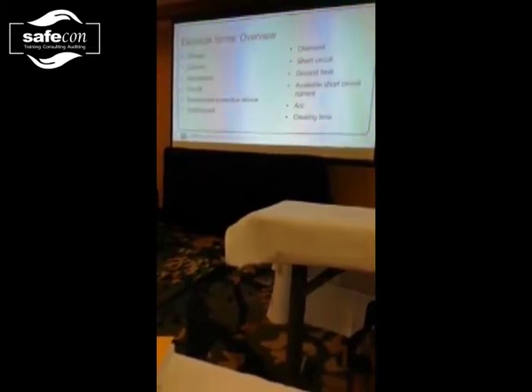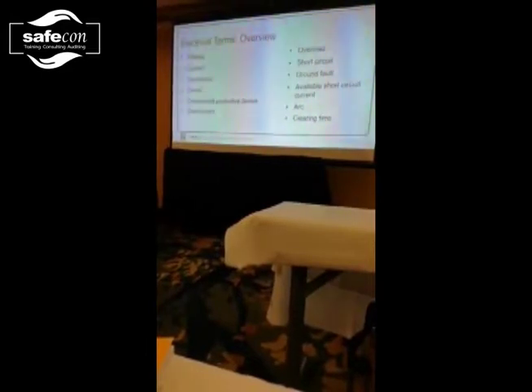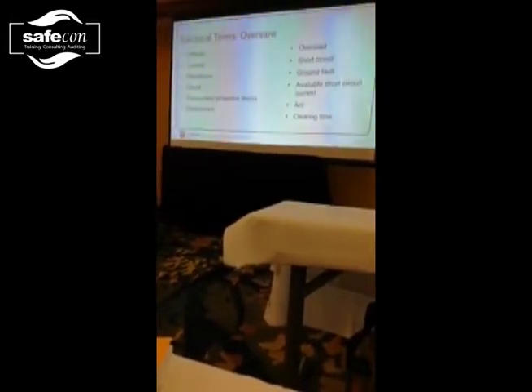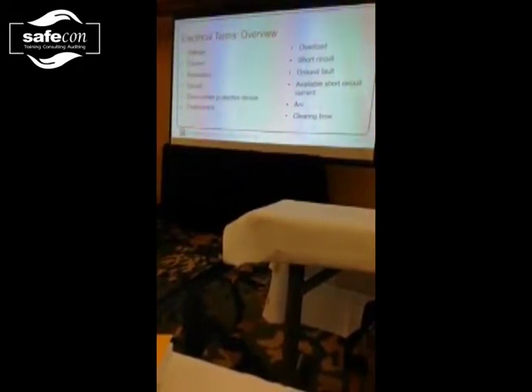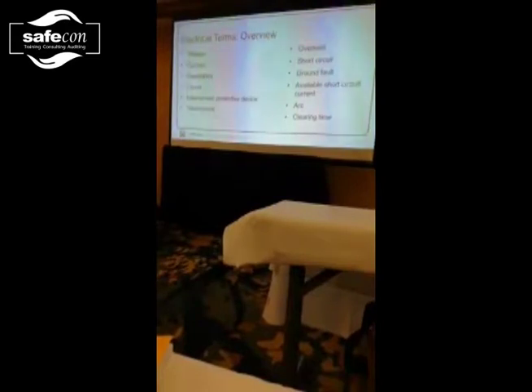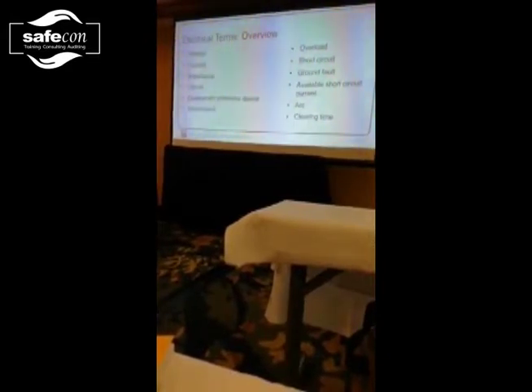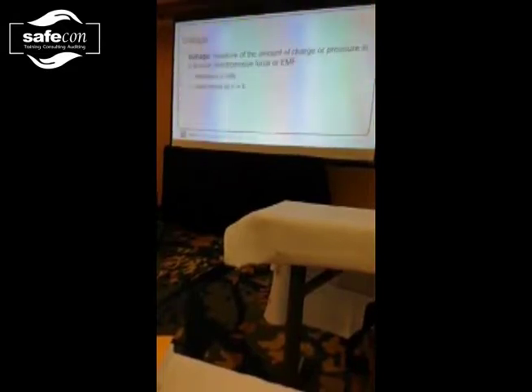So this is the one that I said we'll just kind of go through. I'm just going to put this up here, and then I'll flip through some of the other slides, stopping here and there. We can always talk more about it if somebody feels we need to. But obviously when I think of arc flash, I think of what is the available fault current that's there, how is it going to arc, and how long is it going to arc for. The time is the real key piece of this. Of course, all of the components factor into it, but the longer that the arc continues, the higher the burn energy is going to be, the more heat that's going to be created in that arcing event. So we'll talk more about this as we go through.